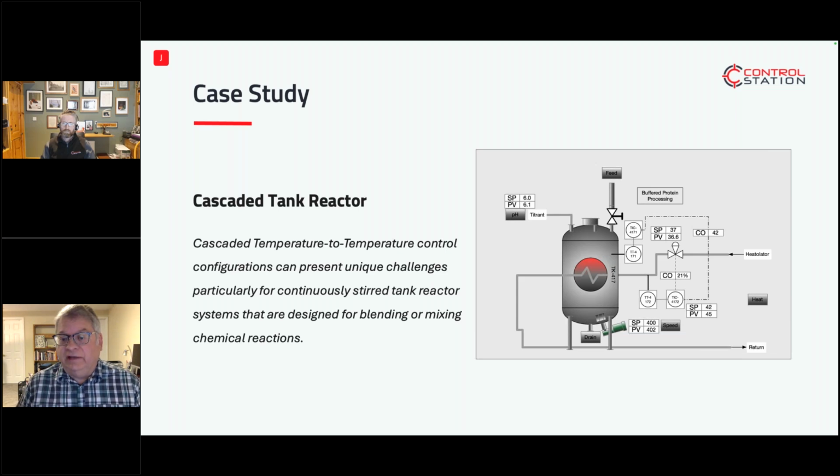So I'm calling for heat, for example, out of this valve coming out of the thermolator. I'm calling for heat through there, but tank 418 is taking that heat. The thermolator is circulating around 45 degrees centigrade. If tank 418 pulls on that demand, the thermolator takes a moment to catch up, and that disturbs my process and can knock me off of temperature. This process is validated plus or minus 2 degrees for the proteins to be considered good and not deactivated.